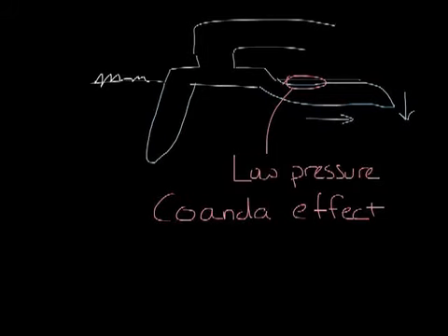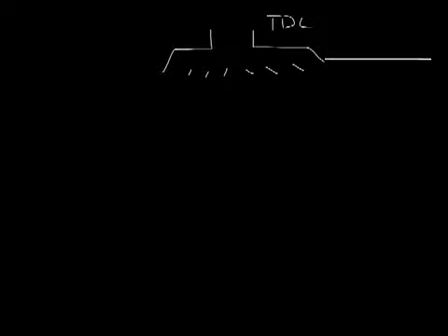So how do you maintain an air pattern without a ceiling? Well, diffusers that perform well in no ceiling applications create low pressure zones inside their backpan. Let's take a minute to look at a couple of diffuser backpans. Let's start with the TDC, which is one of our very common diffusers. The backpan kind of has an angle like this. If you have a ceiling, the airflow looks kind of like this, like before, and you have this little low pressure zone right at the edge of the diffuser where it meets the ceiling.